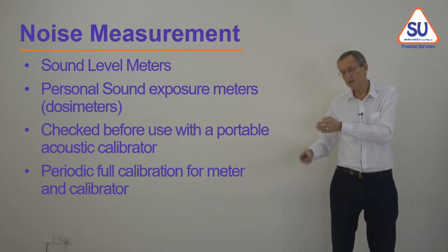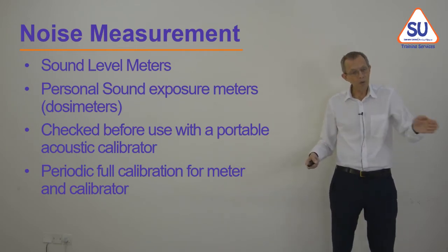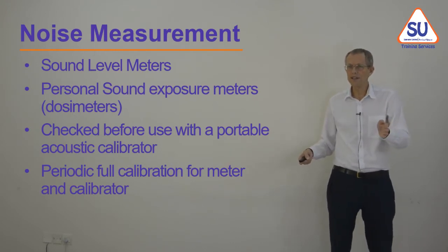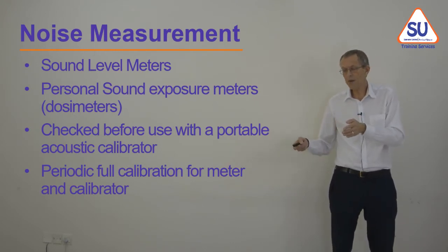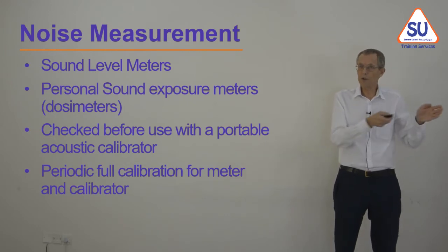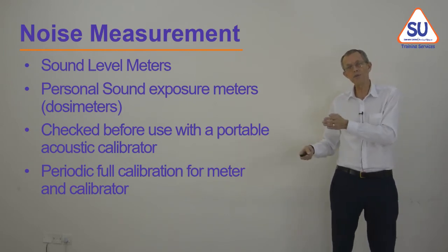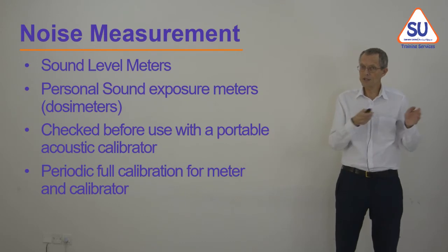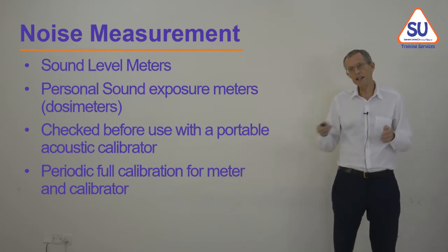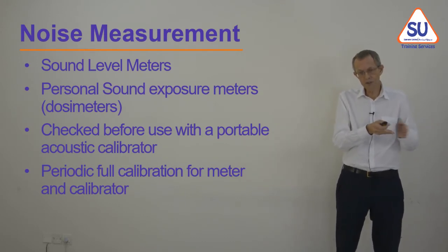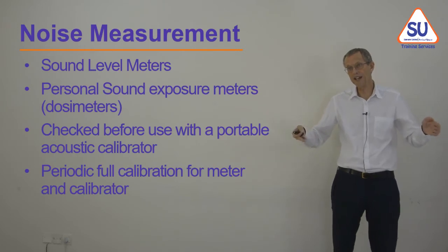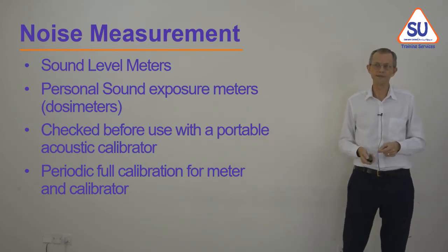It was, let's say, measuring too low. Then I wouldn't know if I could believe any of these results in between, because I don't know when the calibration went wrong, whether it went wrong at the beginning or at the end of the measurement period. So calibration is important, and you need to do it regularly, because we want to be sure that the readings in between the calibration are accurate.